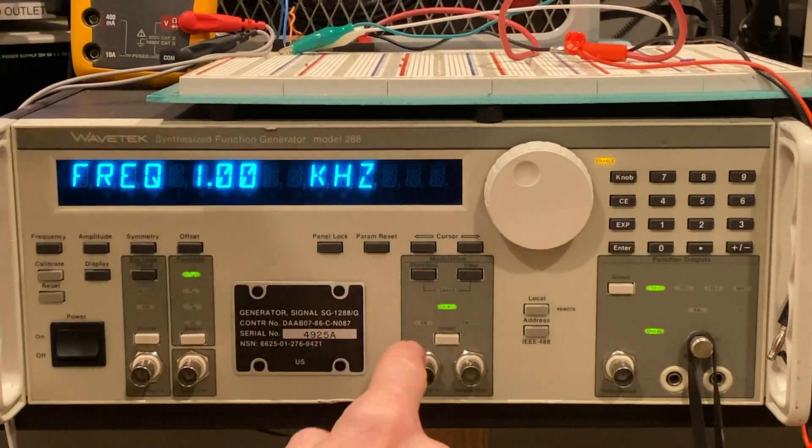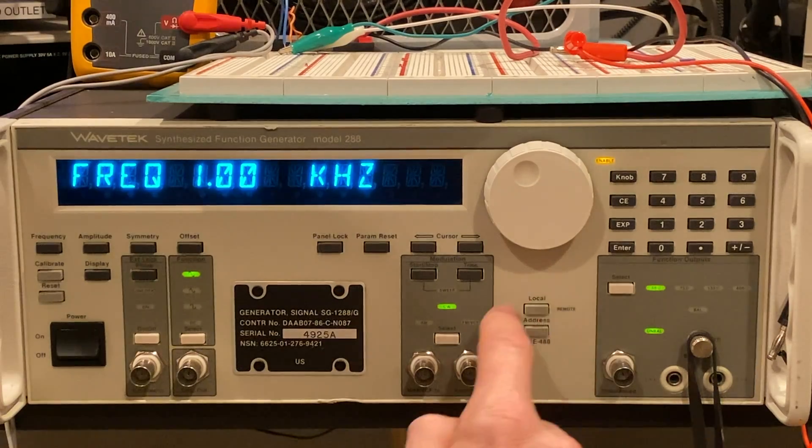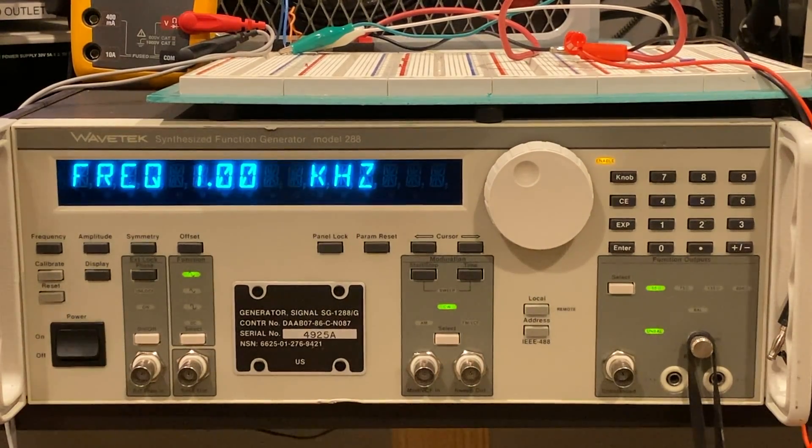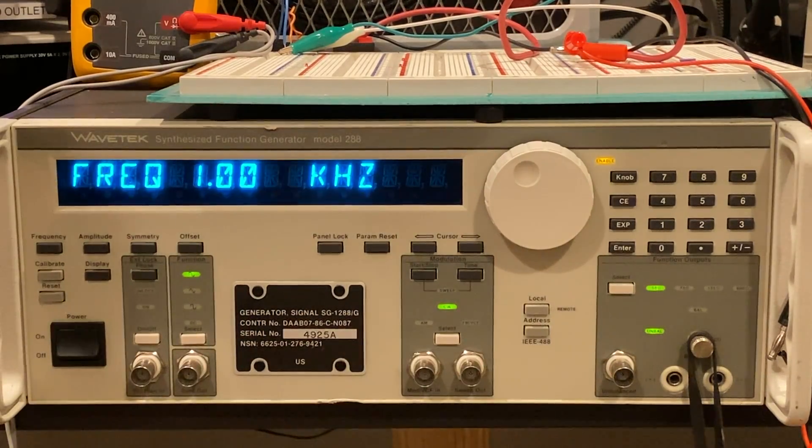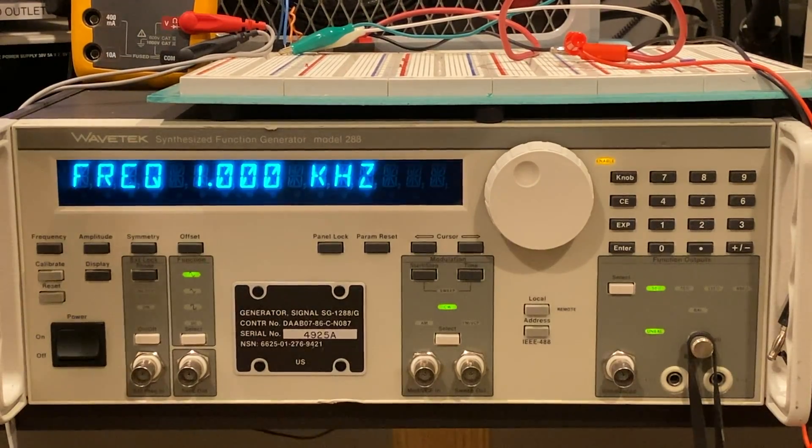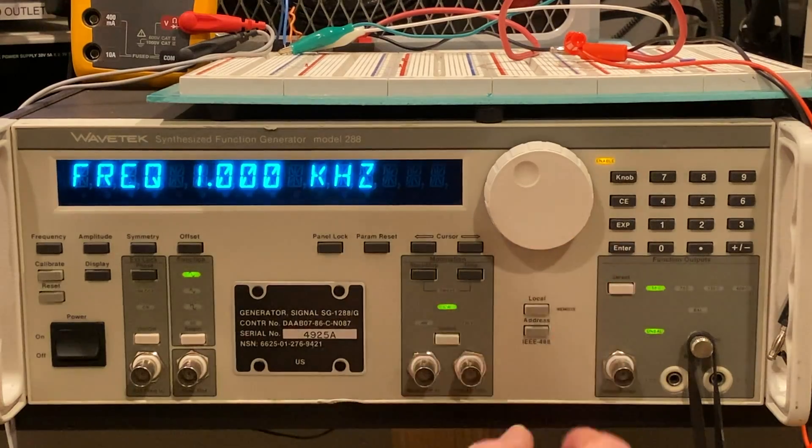Here we have local and address. This is if you have this unit hooked up to a GPIB cable and let's say you want a computer to operate this and you want to control this from a computer. There's a cable output on the back that allows you to talk through the GPIB format.